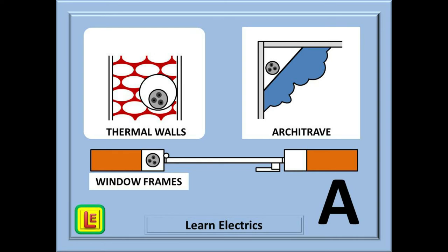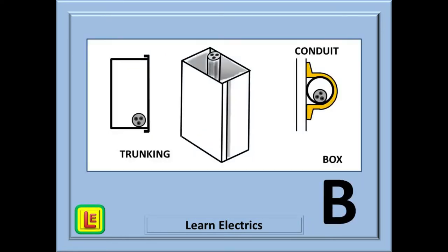Cables installed in trunking and conduit are generally reference method B. Think about this. Trunking is a square box shape. Conduit is a round box shape. That means that B is for box, round box or square box. Hopefully, this is making sense to you. In class at Learn Electrics, this is the moment when our students have a light bulb moment. Everything is dropping into place.